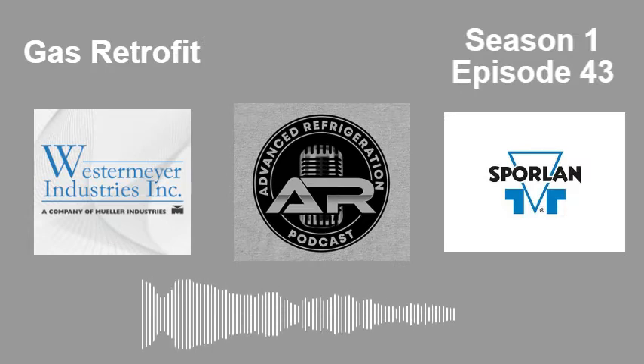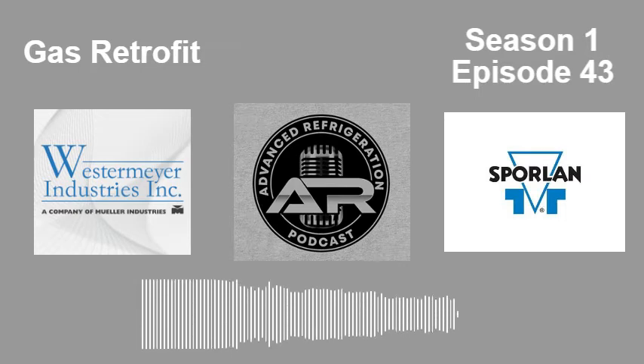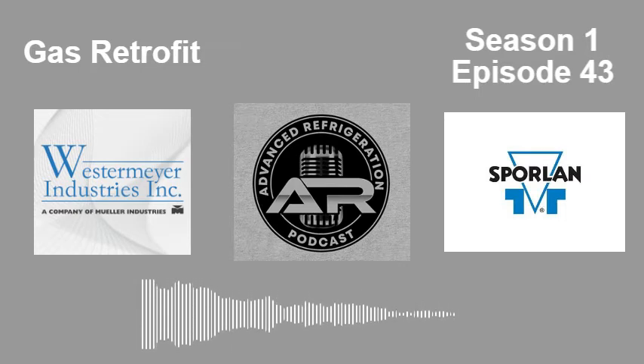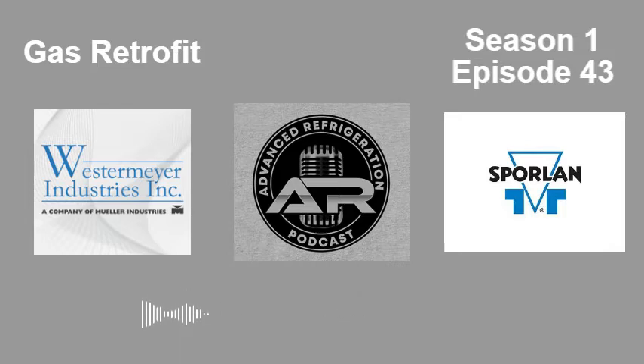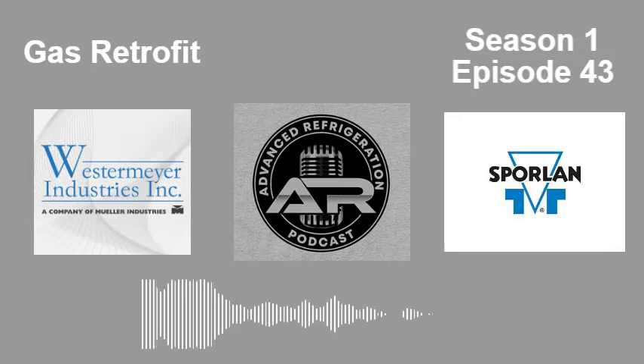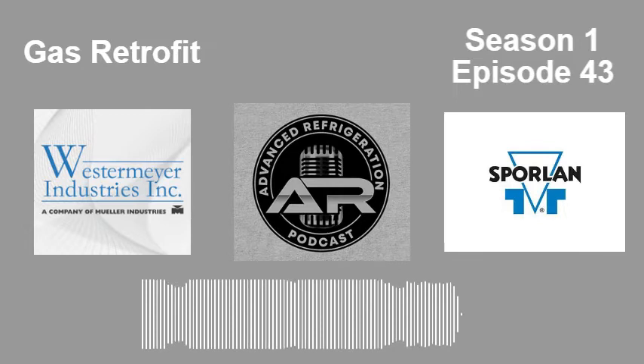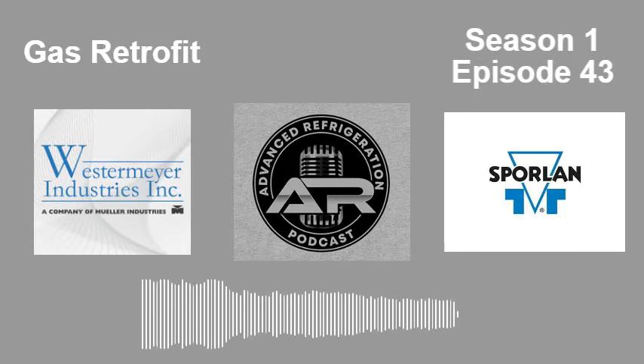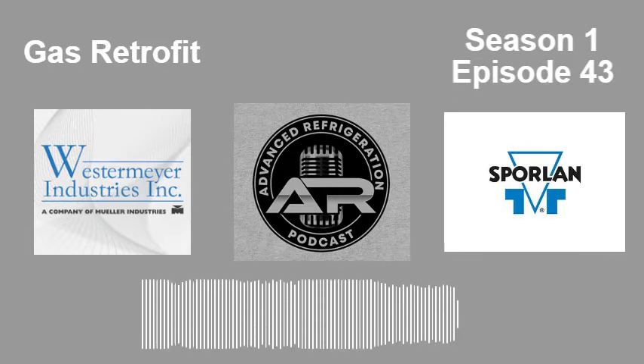So that gets changed. Generally, suction ball valves, if they look okay, I leave them. If they're rusted and look crappy or rounded off, I'll change them. I'm not attacking ball valves that don't look bad. Go ahead. But that's also spec too. Basically you have to just follow whatever the customer is telling you to.